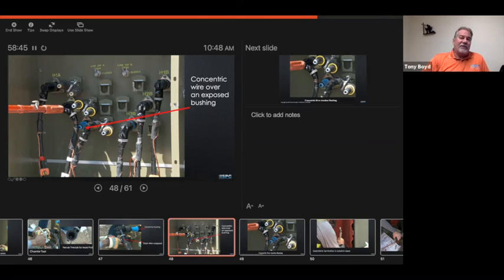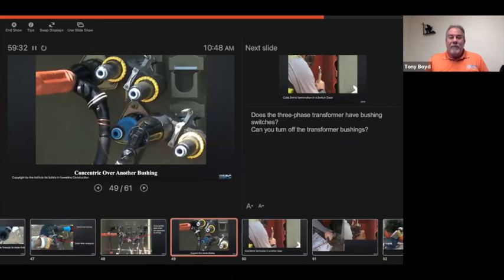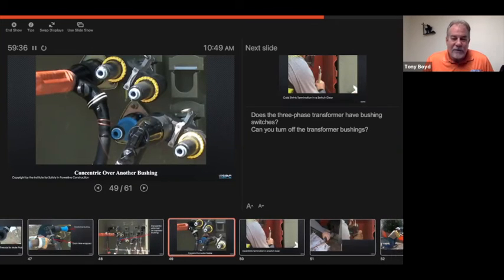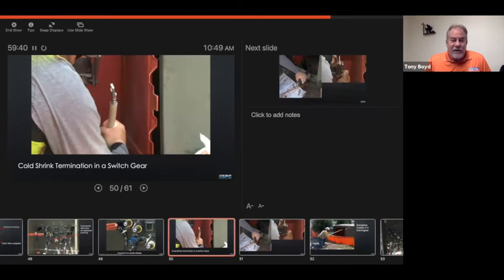If you have a transformer that does not have a switch, and this is plugged in and all of these are energized, we have an energized bushing in the transformer right here. And like I mentioned, the teeth are right close to the end, and depending on the voltage, if we're putting on an elbow and we twist it and we have this grounded concentric wire right over the top, it can arc out and cause a fault. So this should have actually had a bushing cover on it for doing this. They opened the switches and did that, but the company that did this did not actually do this wrong. I had them twisted so that we could get a picture and show what some companies may, in a sense, do wrong. All right. Here's a terminator going into a switch gear.